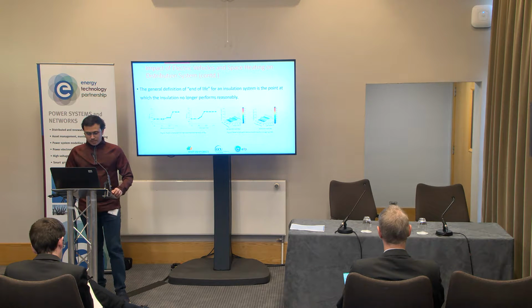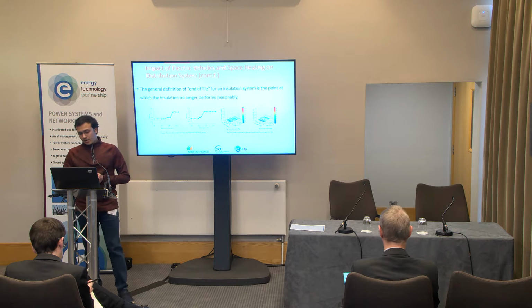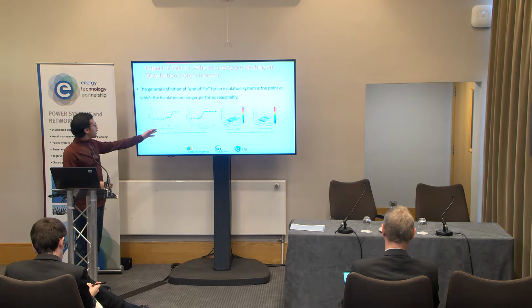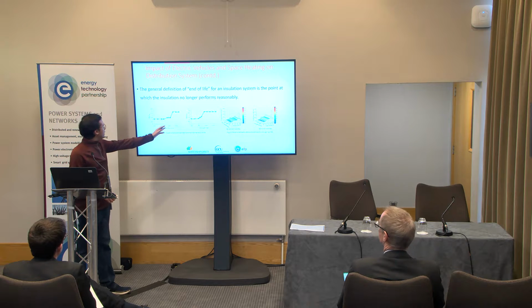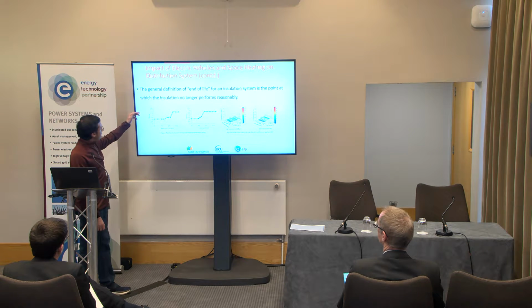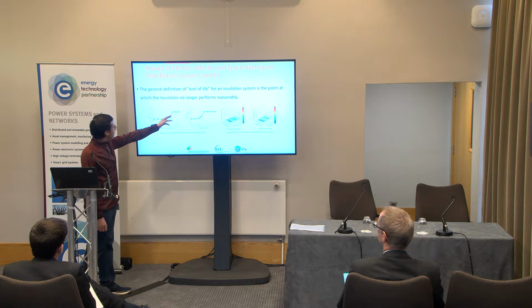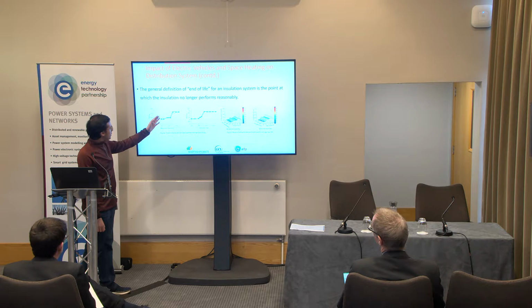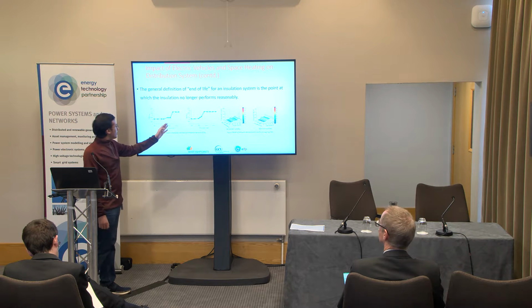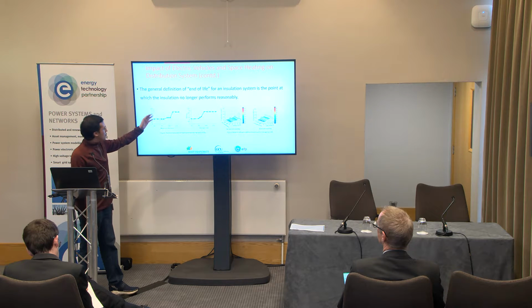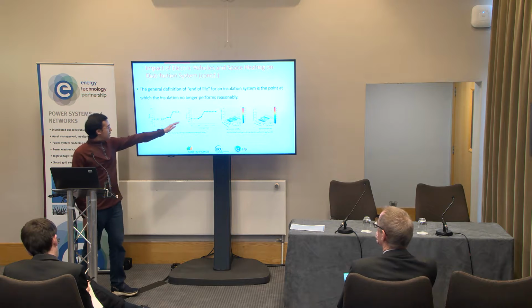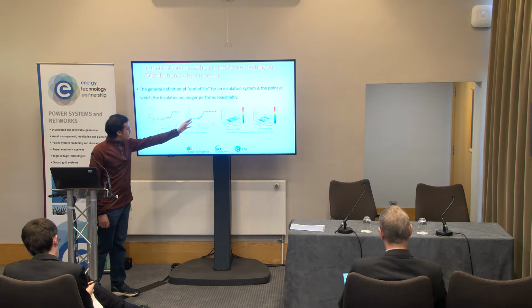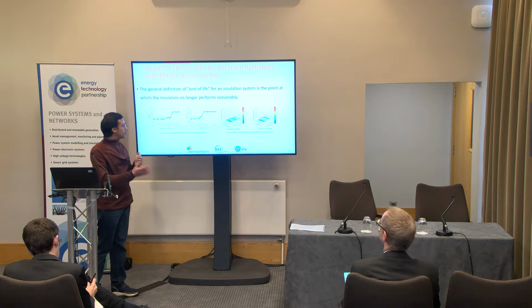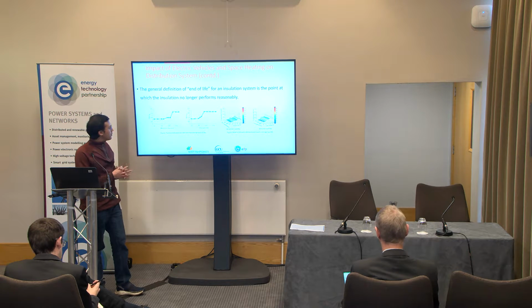Okay, so the general definition of end of life for an insulation system is the point at which the insulation can no longer perform reasonably. Here we see that when the maximum demand is increased over 130%, the transformer end of life can go to number 3, whereas if the maximum demand remains less than 120%, it can be 1. So the maximum demand should be kept less than 120% to have a longer transformer lifespan. And for the average load, we see that less than 80% average load on a transformer is very good. Instead, if we have a higher average load, an overloaded transformer, then its lifespan will be significantly shortened.